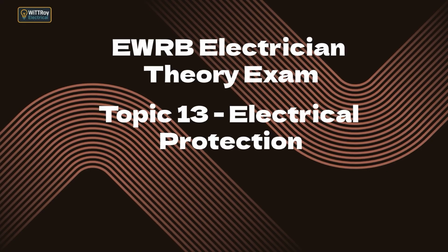13.2I Understand and apply the requirements of AS/NZS 3000 regarding RCD installation and the use of RCDs with handheld electrical appliances. AS/NZS 3000 requires 30 mA RCDs for almost all final subcircuits in homes. Handheld appliances in commercial and industrial workplaces must be RCD protected because the risk of shock increases when tools are held in the hand or used in damp or conductive environments. Tools such as grinders, drills, saws, and site equipment must be powered through RCD protected circuits or PRCDs.